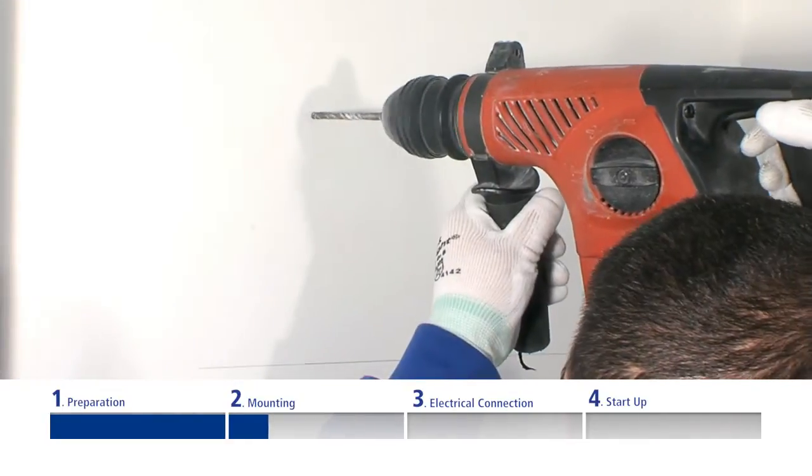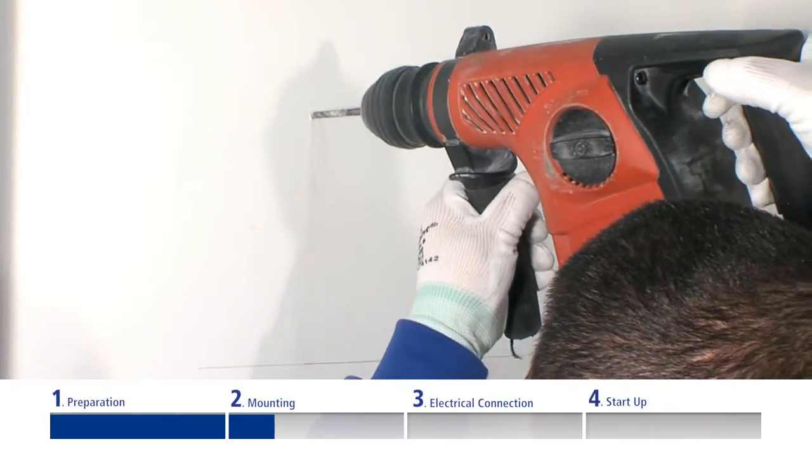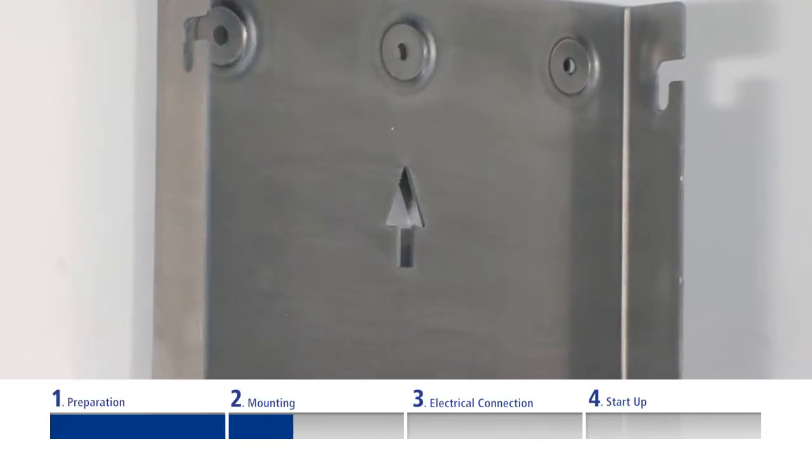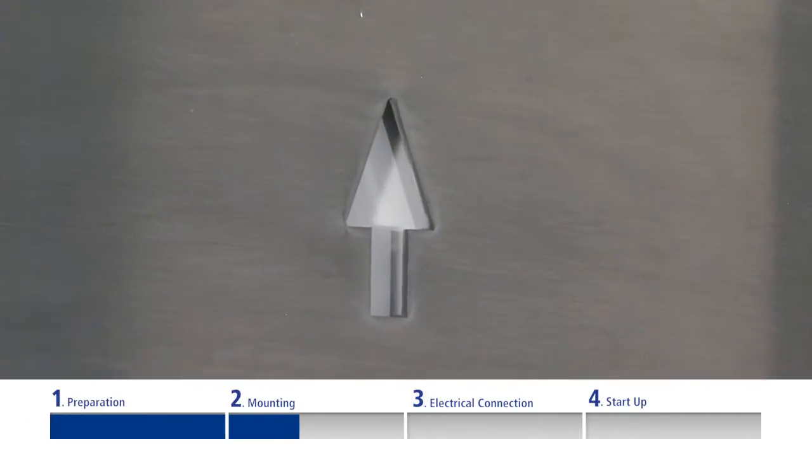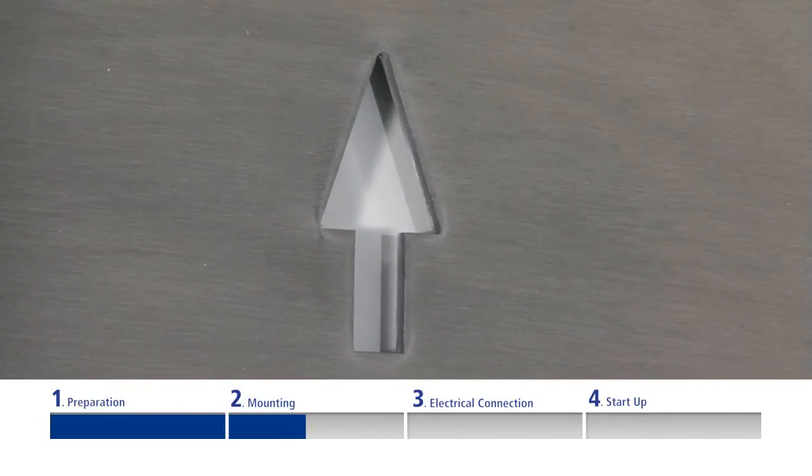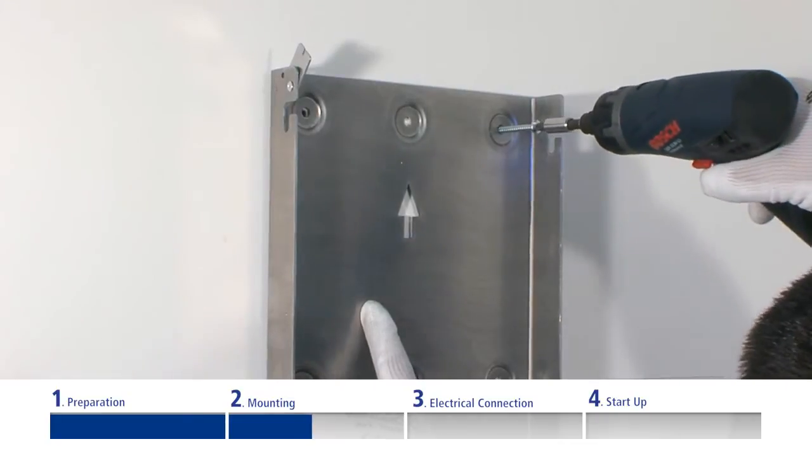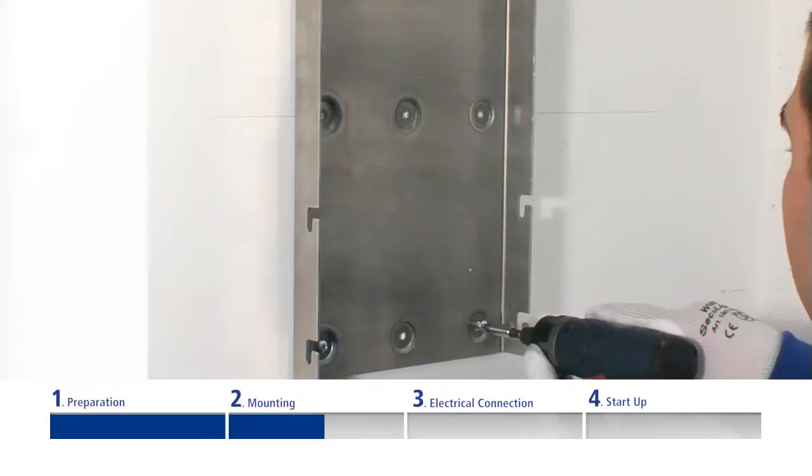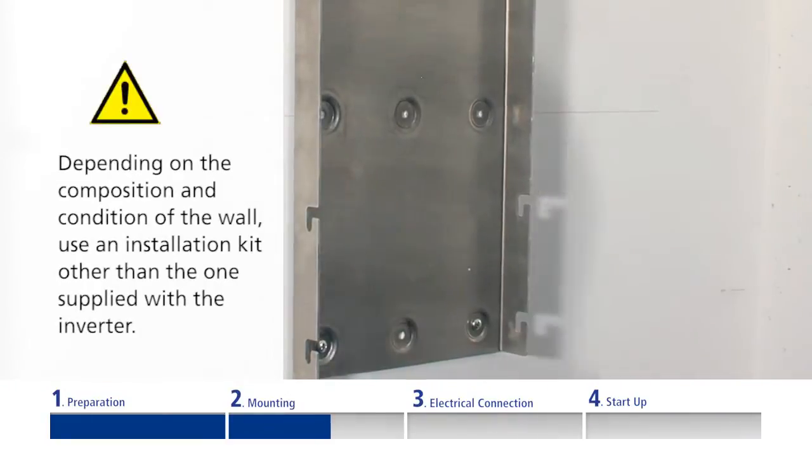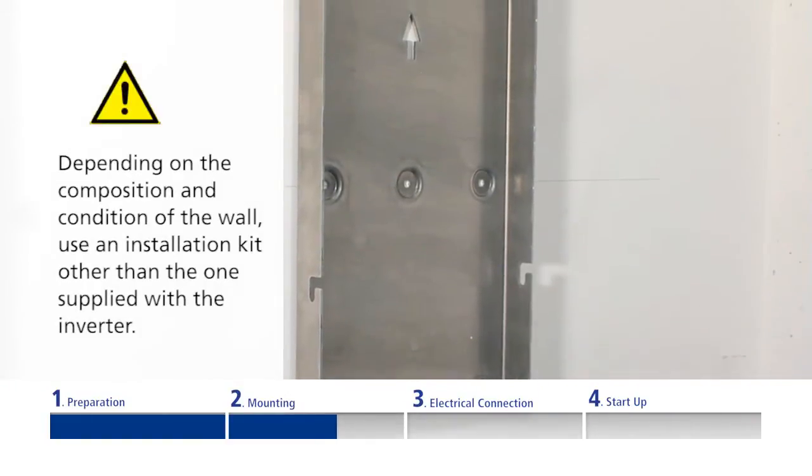Drill the holes and place the fixings into the holes. Secure the wall bracket so that the cut-out arrow in the mounting plate is pointing upwards. Secure the wall bracket using the four accompanying 70mm screws. If necessary, depending on the composition and condition of the wall, use a different installation kit.